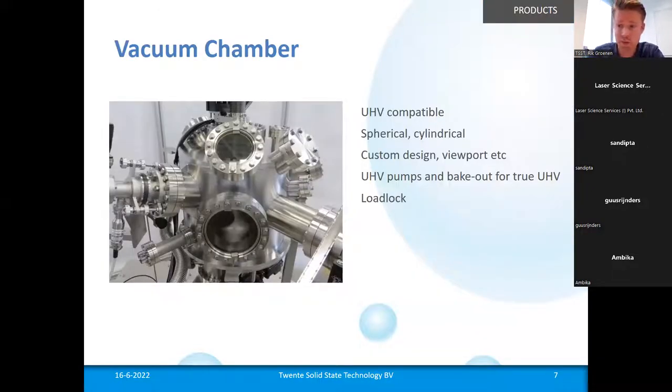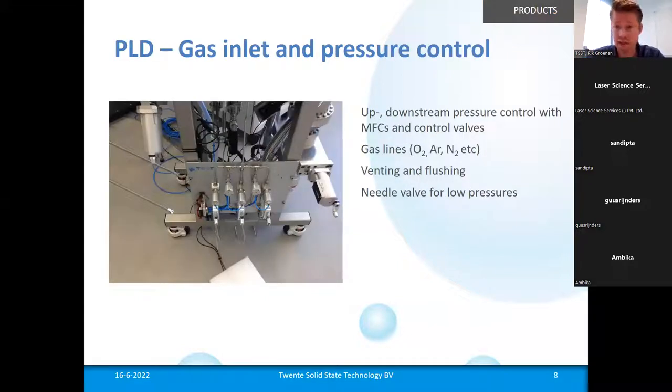Just briefly going into the machine itself. The core is a vacuum chamber. You want to work in a clean environment, which is always custom designed, so we can add ports wherever you want. We can prepare the system for future upgrades, load locks, etc.